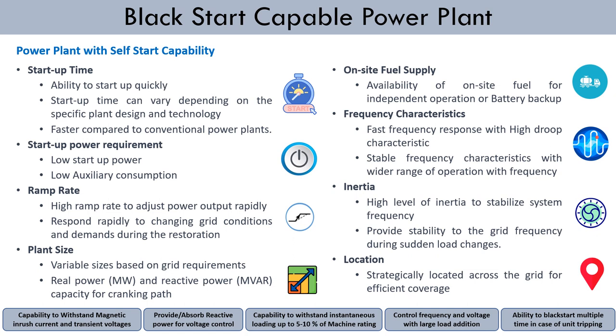Frequency characteristics. Black Start Capable Power Plants are designed to have stable frequency characteristics and the ability to operate during frequency excursions. They maintain grid frequency within acceptable limits and adjust their power output to match the system demand as it stabilizes after the blackout. Inertia. Inertia is the ability of a power plant to provide stability to the grid frequency during sudden load changes. Black Start Capable Power Plants are typically equipped with synchronous generators that have a high level of inertia. This inertia helps to stabilize the system frequency and prevent large frequency deviations during the restoration process.